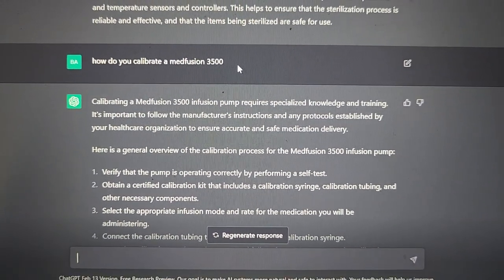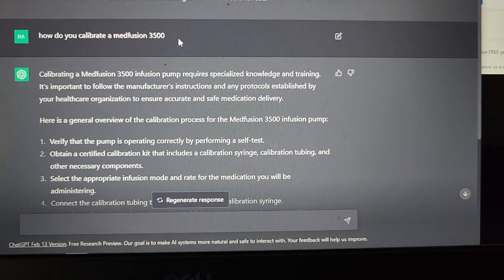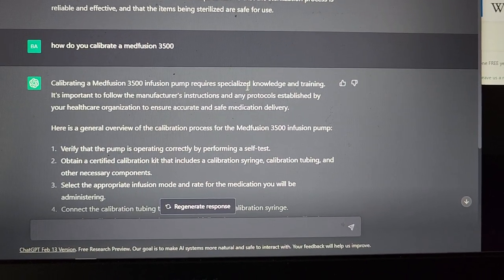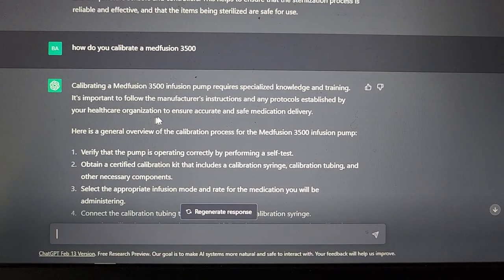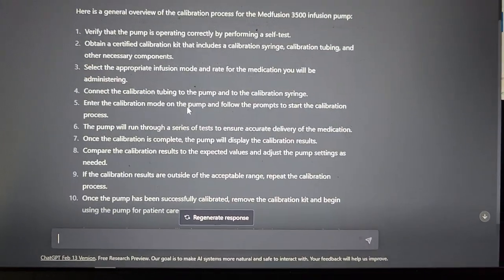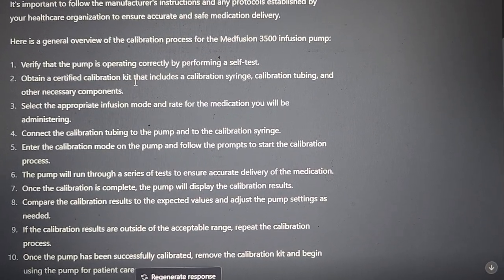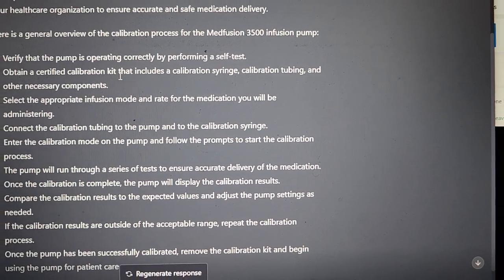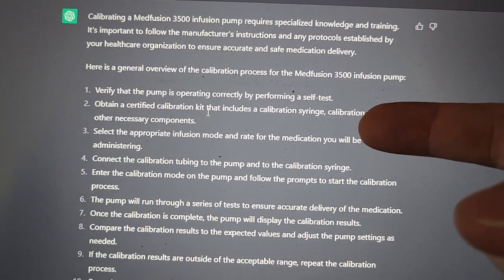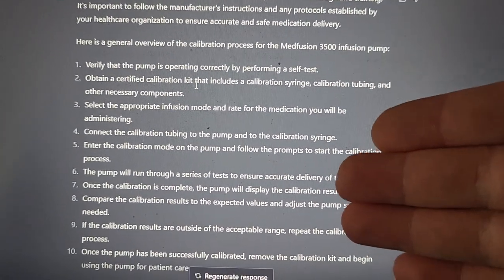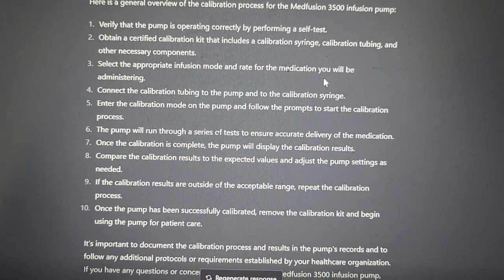My last question: how do you calibrate a Medfusion 3500? It started with the politically correct answer — 'it requires special knowledge and training, follow the manufacturer's instructions' — and I thought that was going to be it. But then it continued on and actually gave me a process. It says, 'Here's a good overview of the calibration process for the Medfusion 3500,' and you can see it goes through the self-test and talks about the calibration kit. This is extremely thorough.